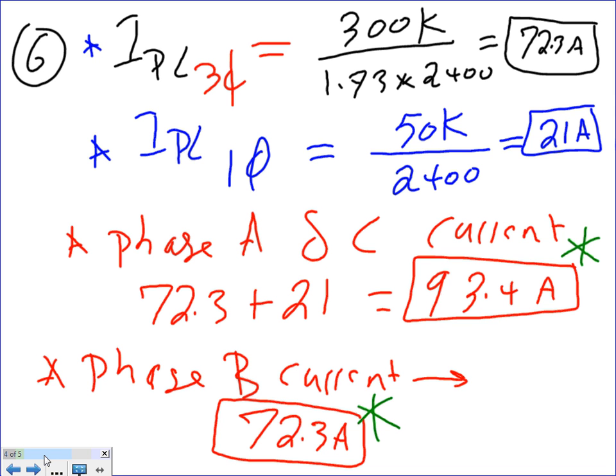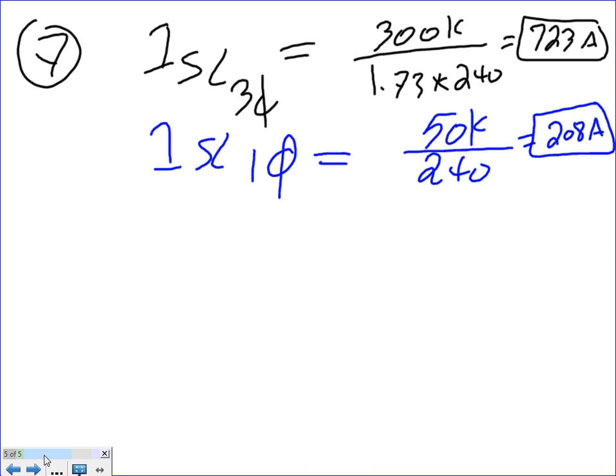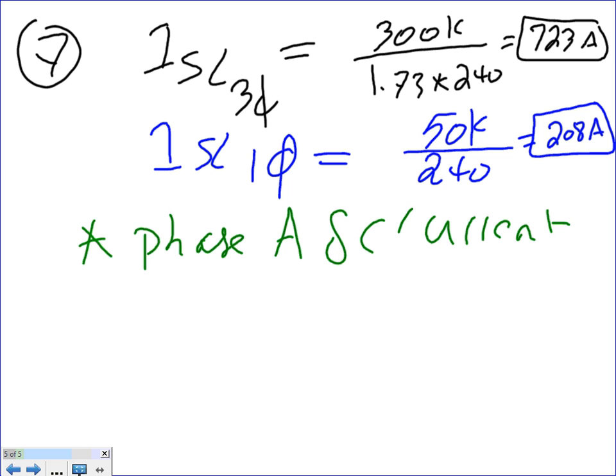This, guys, will see both of them, A and C. B is going to see only one, the 3-phase. I'm going to repeat this for the secondary side: for phase A and C current, what do you guys think phase A and C current is going to carry? 723 plus 208. The 2 phases are going to carry 931.